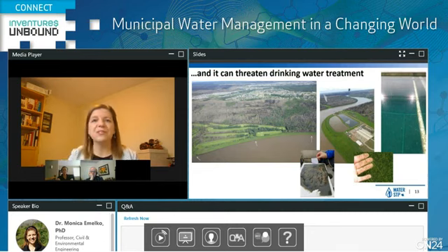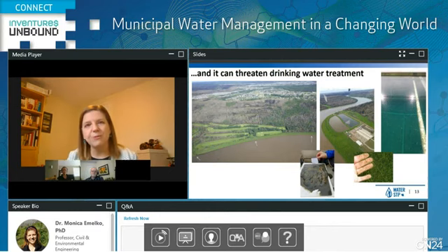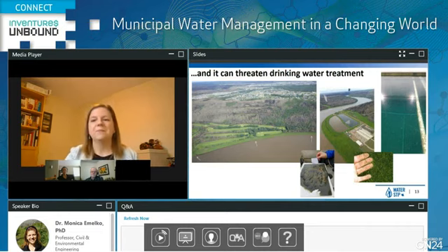And yet after the fire, we saw very real impacts in Fort McMurray, where we saw increases of 50% or more in chemical coagulant demands, and the occurrence of annual potentially toxin-forming algal blooms in the source water that they have not experienced regularly. And you can see some of the images on the right, literally the tanks looking green because of those algal blooms. So these challenges can threaten public health if they're not adequately managed. And fortunately, we've been able to do that in Fort McMurray, but there's a cost to it.